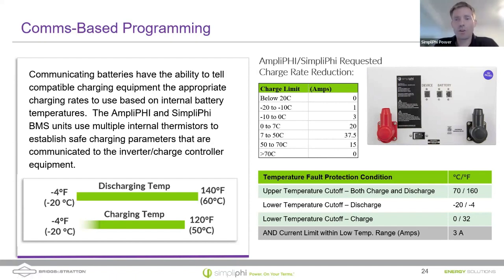What happens when you start charging a battery is the temperature of the cells starts to warm up. The AmpliPHI BMS monitors the temperature of the BMS and the cells and cell packs in a number of different locations. As those cells warm, even though outside temperature might still stay at -20°C or below, the battery cell temperature will start to increase. It charges at 1 amp for a while until the cell temperature comes up higher, and as that cell temperature reaches -10°C, it switches to 3 amps. As the temperature rises even more, it'll switch to 20 amps, and eventually it'll be charging at 37.5 amps.